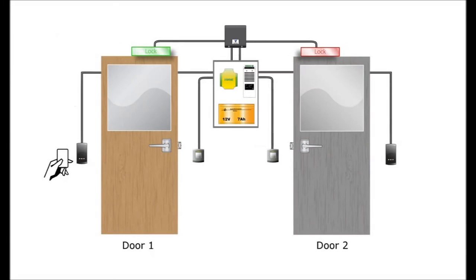So, provided door 2 is closed, when a token is presented to door 1, door 1 will unlock and can be opened. If however door 2 is open, a token presented, whether valid or not, will not unlock door 1.